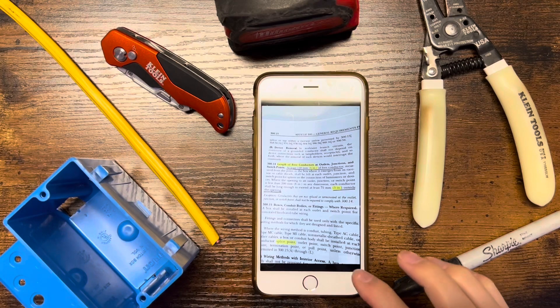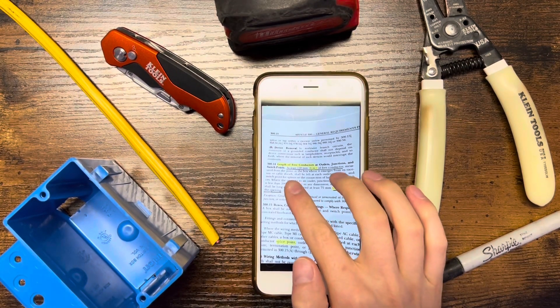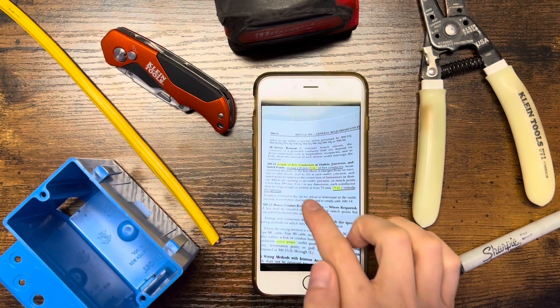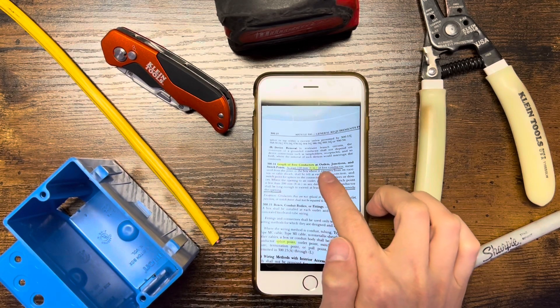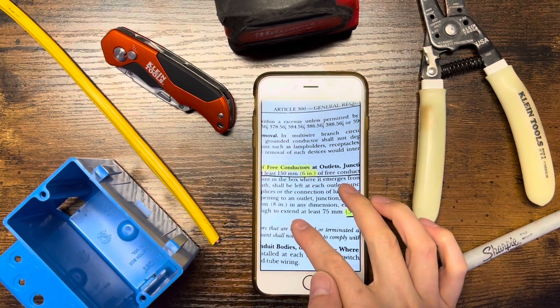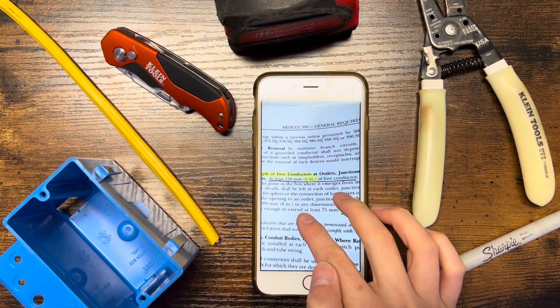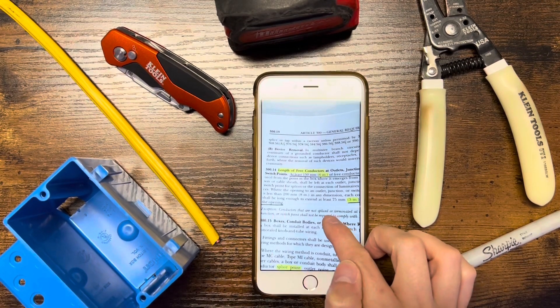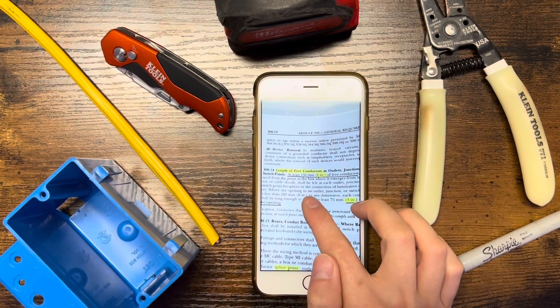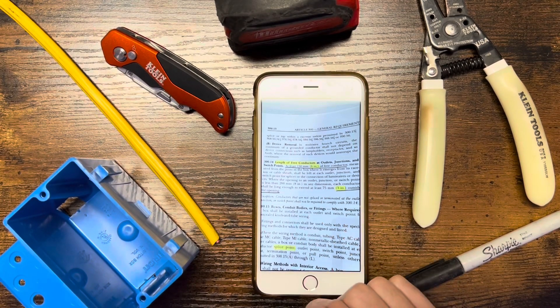This is a picture sent from Steven from his codebook, which is the latest version that he just used to take his test. Code Article 300.14: length of free conductors at outlets, junctions, and switch points. As you can see, underlined: at least 150 millimeters — 6 inches of free conductor — measuring from the point in the box where it emerges from its raceway or cable sheath.